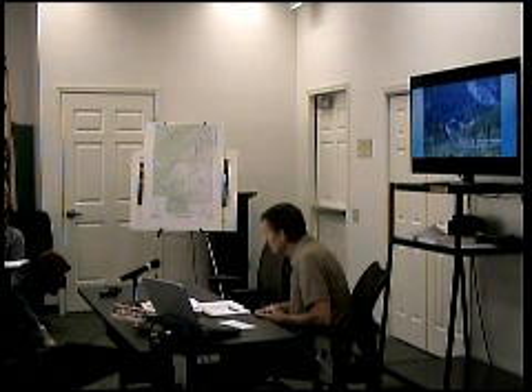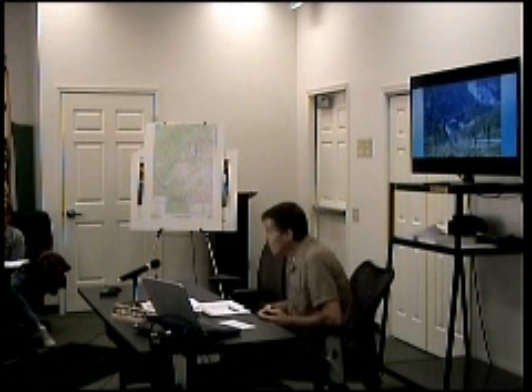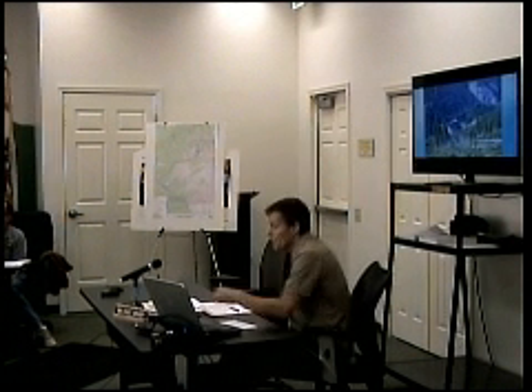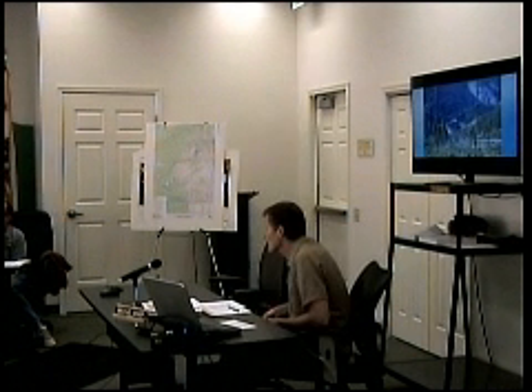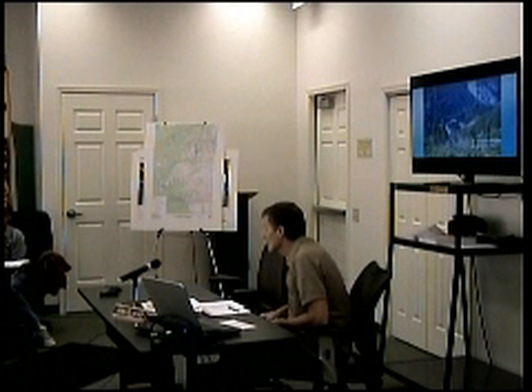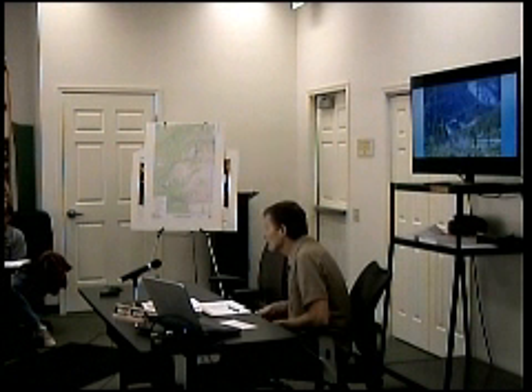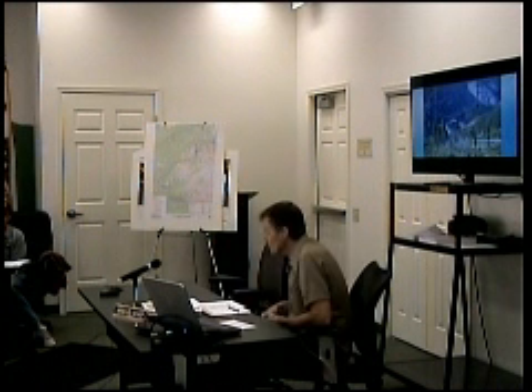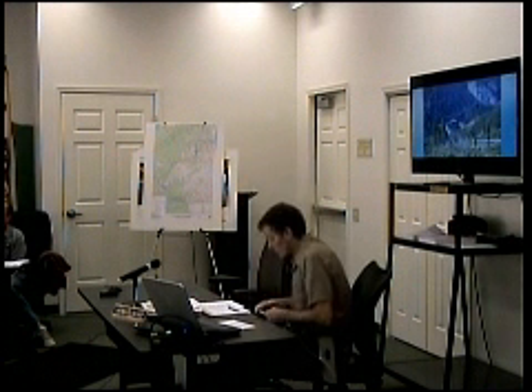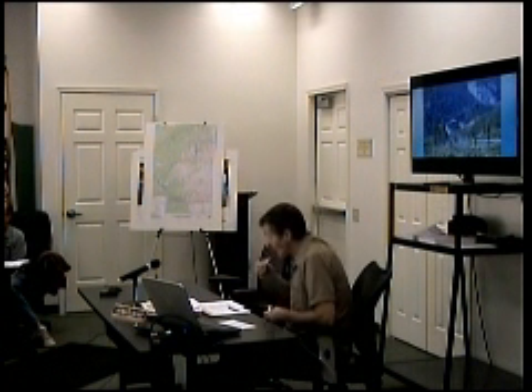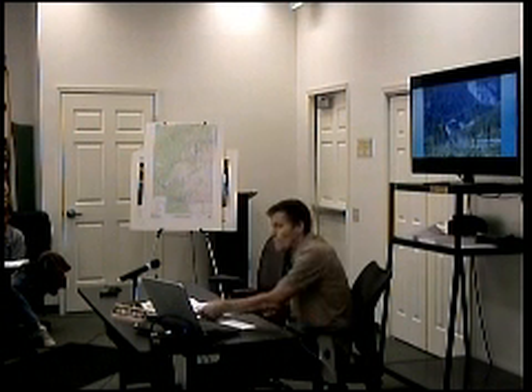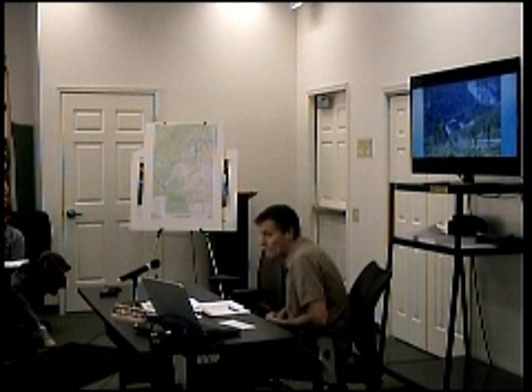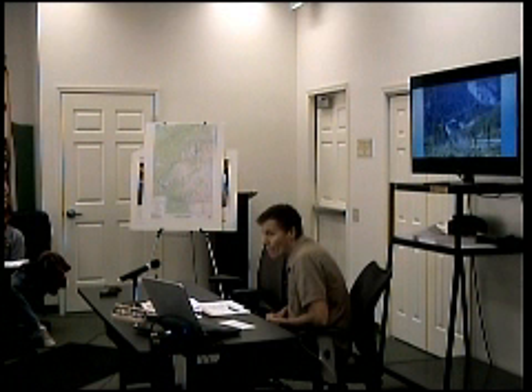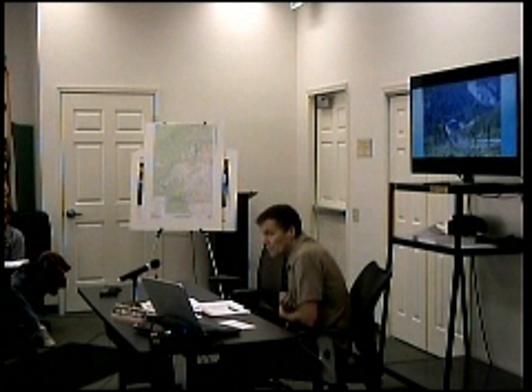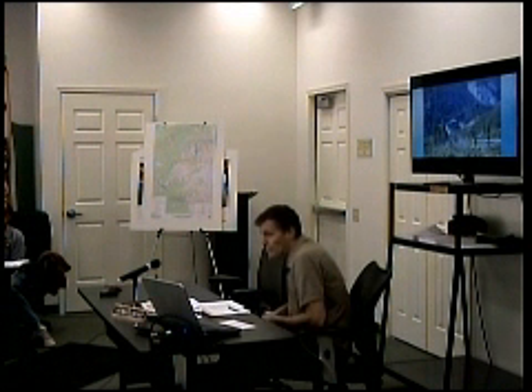So that would be typically for scheduled maintenance. Right. You need to do some work on the line, you get your generators on, you switch them over, you de-energize the line, do your work, and come back. And during the short period when they're both operating, we're not sending power? According to the PG&E handbook, and in multiple discussions with PG&E, you are allowed to have very short-term paralleling, and that's the tweaking that I'm talking about.